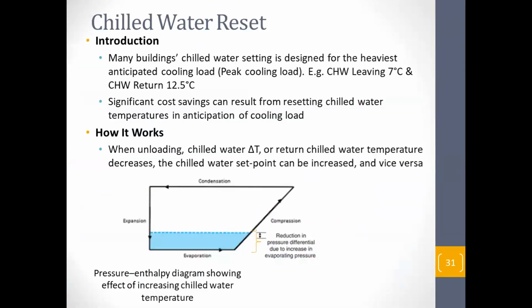Number one is done. The next one is chilled water reset. Running chill water at a higher temperature is a good option. I learned this way back in 1998 when I was reading an ASHRAE journal, and from that day onwards, we were running our chillers at an elevated temperature. When you increase your chill water temperature, it will increase the evaporating pressure. When the evaporating pressure is higher, your compressor doesn't have to work as hard. It has to work less. That's why I have illustrated this in this particular diagram. But you have to be careful on that.